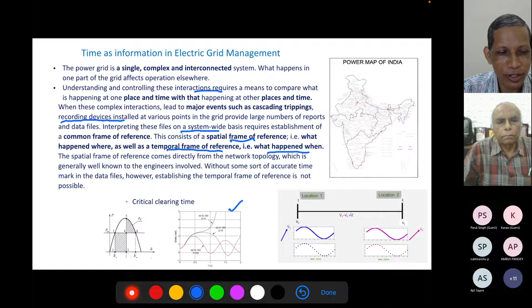With critical clearing time, the sooner the fault is cleared, the better it is. In 400 kV, 765 kV, and 800 kV systems, we are left with only a few milliseconds to clear those faults, otherwise the system may go unstable.